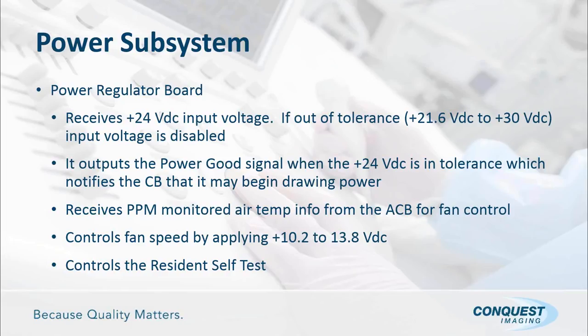It does receive monitored air temp information from the acquisition control board for fan control, and adjusts the fan voltage from 10.2 to 13.8 volts DC to appropriately cool the system off. It also controls the resident self-test. So if you're having problems with the resident self-test, that resides on the power regulator board.